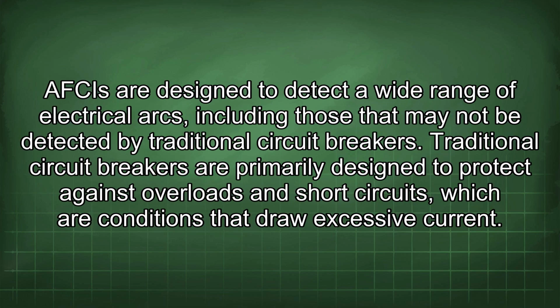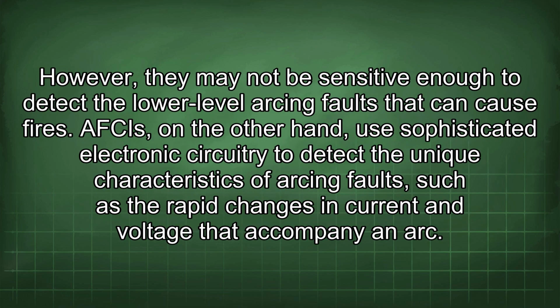AFCIs are designed to detect a wide range of electrical arcs, including those that may not be detected by traditional circuit breakers. Traditional circuit breakers are primarily designed to protect against overloads and short circuits, which are conditions that draw excessive current. However, they may not be sensitive enough to detect the lower level arcing faults that can cause fires. AFCIs, on the other hand, use sophisticated electronic circuitry to detect the unique characteristics of arcing faults, such as the rapid changes in current and voltage that accompany an arc.